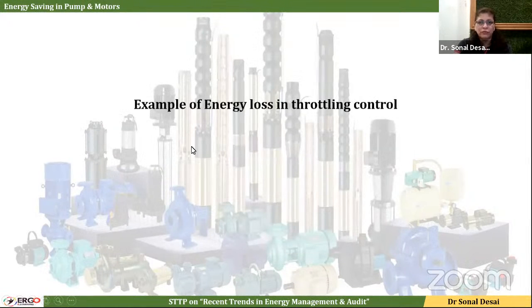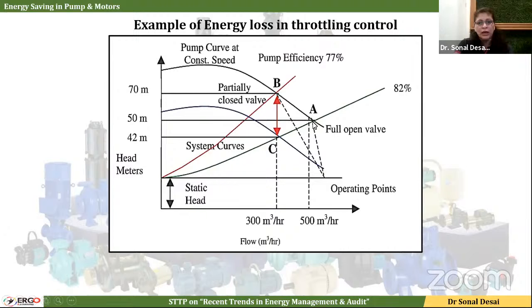To understand the same, one more example is here. Let us say the pump is operating initially at condition A. This condition A gives me a flow rate of 500 meter cube per hour and it is delivering a head of 50 meter. At this point, pump efficiency is 82%. This is a good efficiency because here my system curve and the pump curve are matching and it is almost near my best efficiency point.